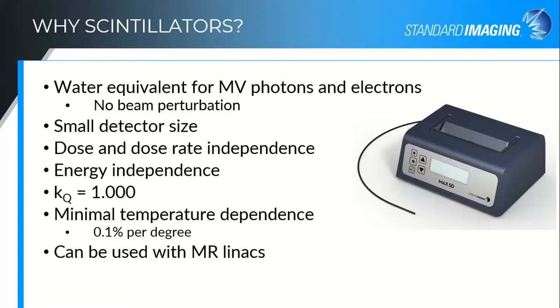For these megavoltage photons and electrons, we're not seeing dose or dose rate dependencies, which simplifies the measurements so that you don't have to correct for or watch out for those changes. As dose rates are increasing and we're looking at very high doses in a short amount of time, that's also an interesting avenue to pursue. The energy independence and the beam quality correction factor of unity really reflect back to that water equivalence for these beams.